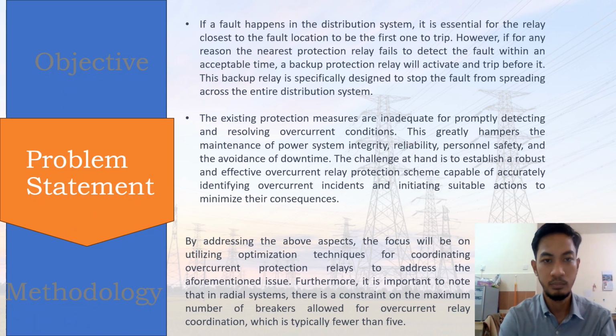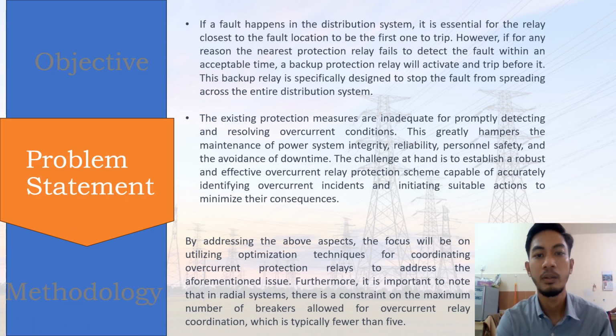Problem statement. If a fault happens in the distribution system, it is essential for the relay closest to the fault location to trip first. However, if for any reason the nearest protection fails to detect the fault within an acceptable time, a backup protection relay will activate and trip. This backup relay is specially designed to stop the fault from spreading across the entire system.